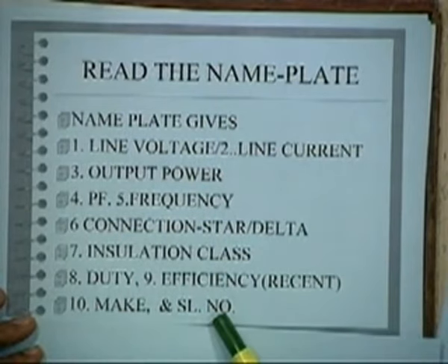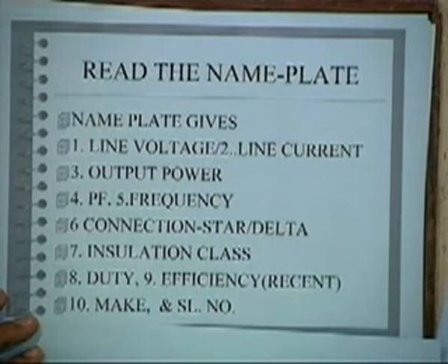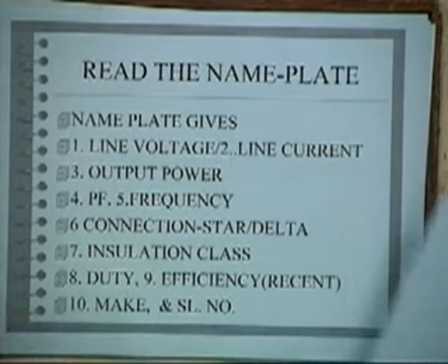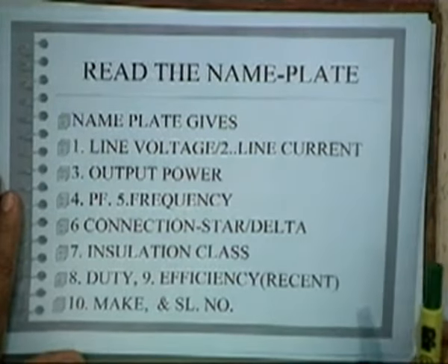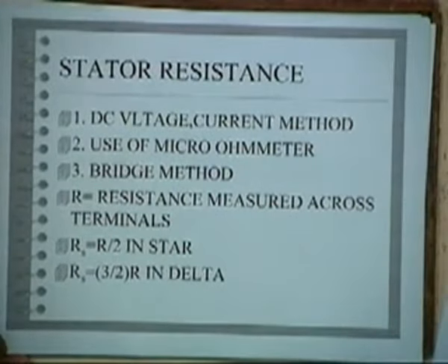And the serial number is also important, because if you tell the manufacturer the serial number, maybe he will be able to find out when it was manufactured and what the design was, because the manufacturer's design department will have the data on the designs for different series of motors. So these are of practical importance, which are not often discussed in textbooks. Therefore, this is what you will have to know.